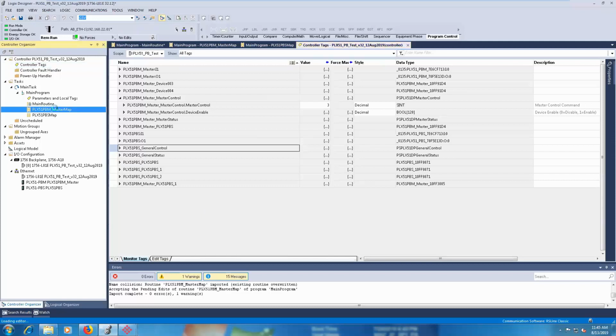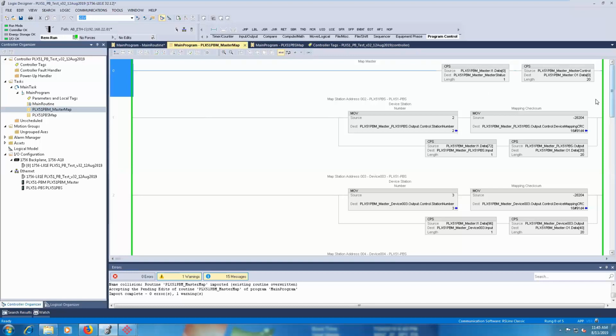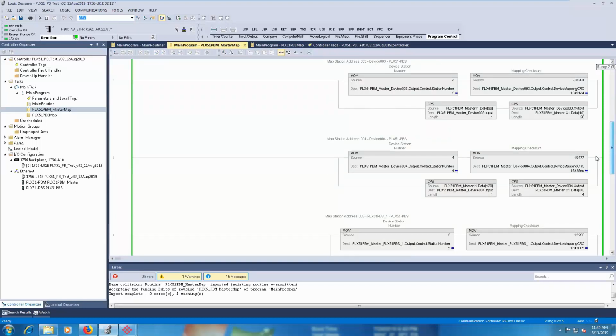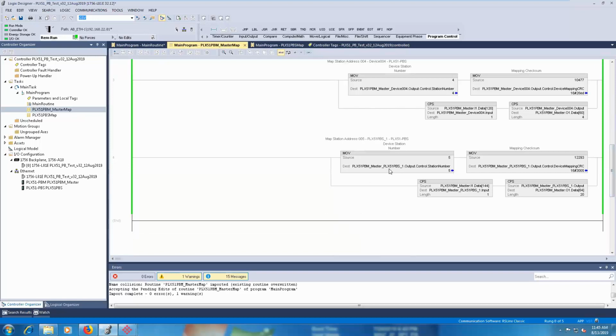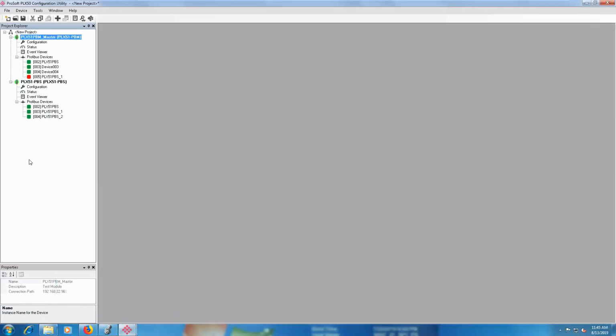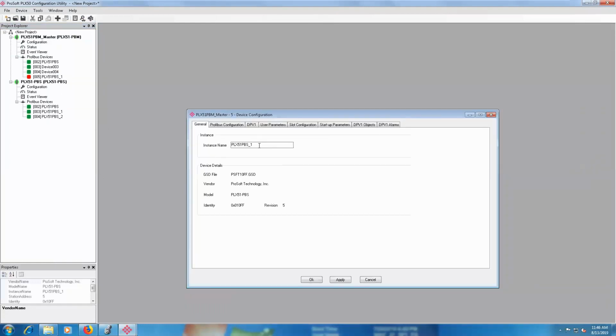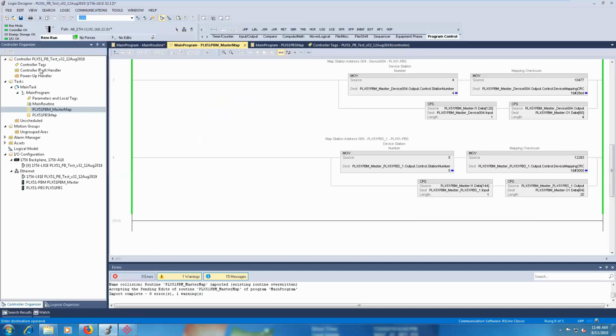And so what I've done now is I've got a custom routine that essentially does my data mapping, and added my tag in here for a PLX51 PBS_1, which was based on the name I gave it right here. It's actually recommended before importing that you change this to something that's going to make a little bit more sense in your application. You could say node 5, you could say drive 3. Whatever name you give it is going to be how it gets imported into the Logix environment.